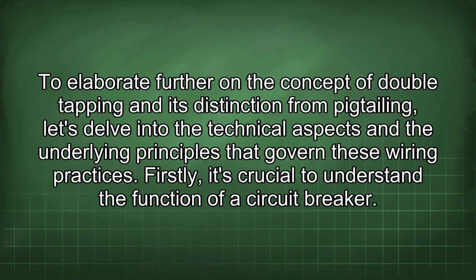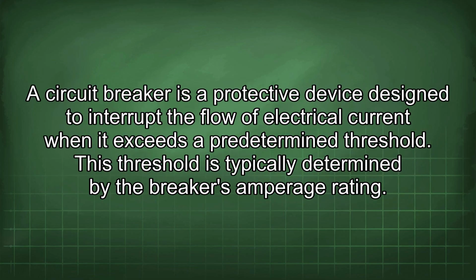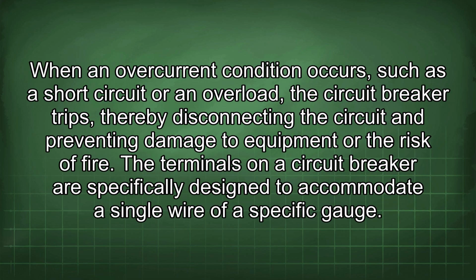To elaborate further on the concept of double tapping and its distinction from pigtailing, let's delve into the technical aspects and the underlying principles that govern these wiring practices. Firstly, it's crucial to understand the function of a circuit breaker. A circuit breaker is a protective device designed to interrupt the flow of electrical current when it exceeds a predetermined threshold. This threshold is typically determined by the breaker's amperage rating. When an overcurrent condition occurs, such as a short circuit or an overload, the circuit breaker trips, thereby disconnecting the circuit and preventing damage to equipment or the risk of fire.